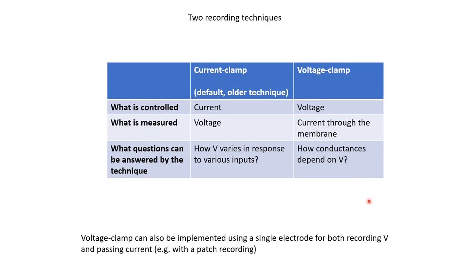In the previous slide we saw one recording electrode and one current-passing electrode for voltage clamp. However, both functions can be performed by the same electrode, so one can do patch recordings in voltage clamp mode with just a single electrode. This requires some sophisticated electronic circuit design, but commercial amplifiers that achieve this are now available.